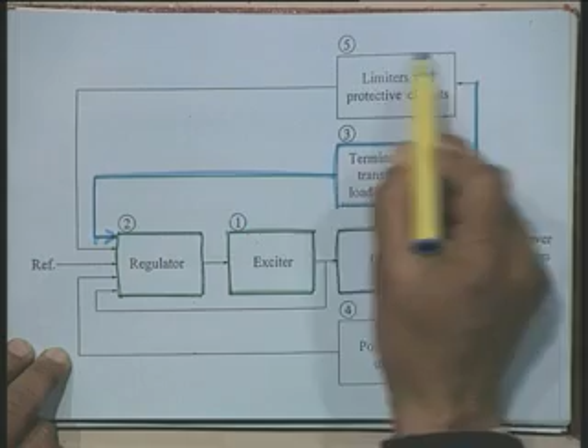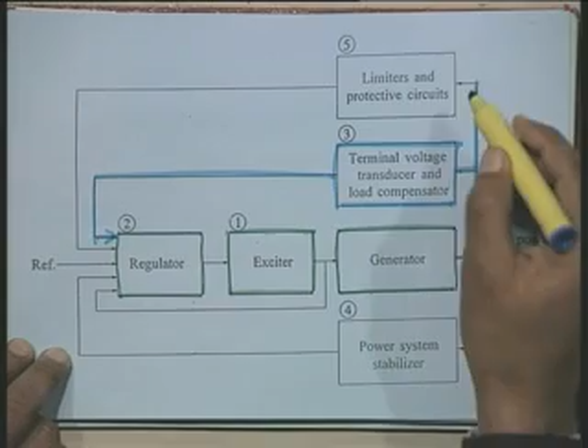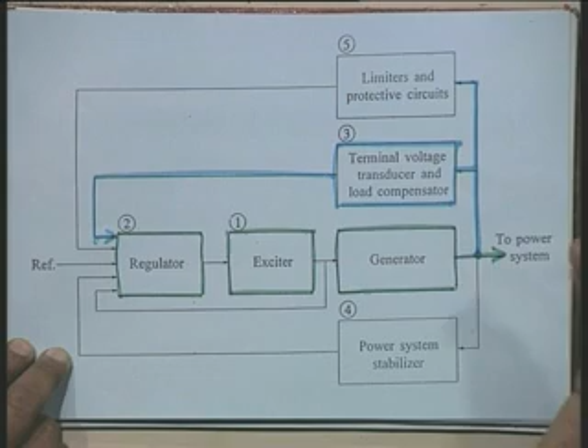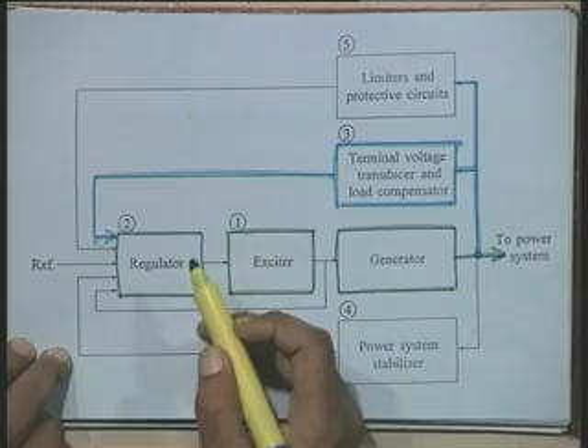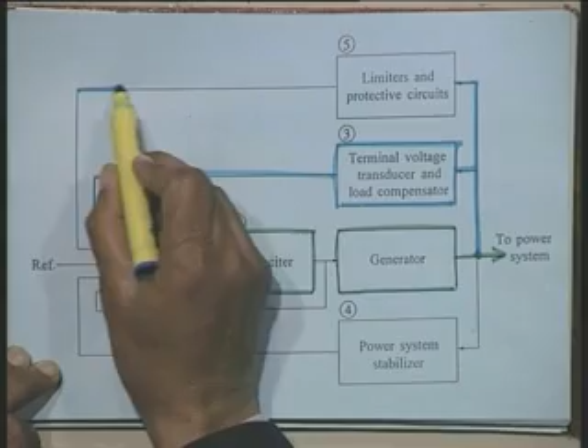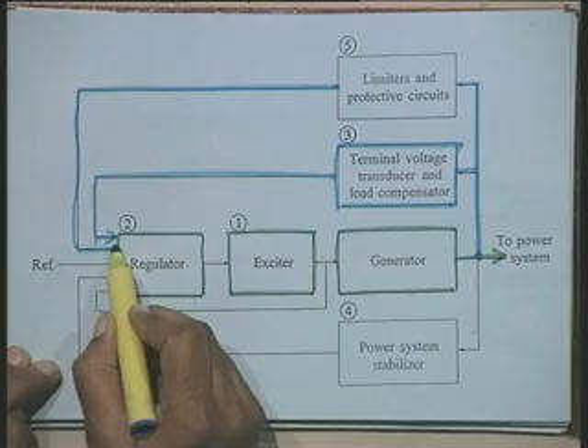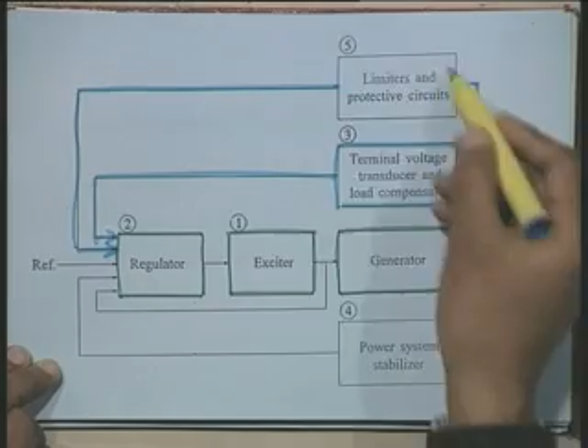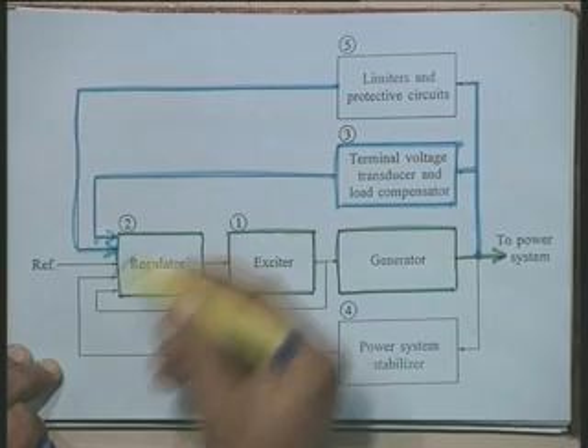Okay. The second block which I have shown here is the limiters and protective circuits. Now, the limiters will also sense the terminal voltage and load current, okay, and it is going to process these signals, current and voltage, which are sensed from the terminal of the machine, and then decide whether the synchronous generator operating condition is within the limits or not. In case it is going outside the limit, it will take appropriate action. Again the action is taken through the regulator. Therefore, this signal which is coming from the limiters and protective devices also is fed to the regulator.